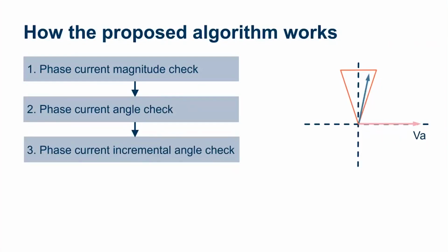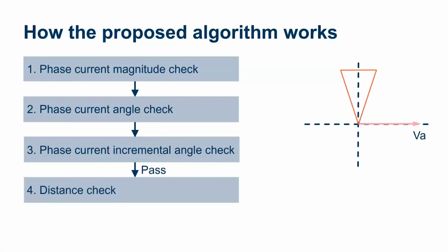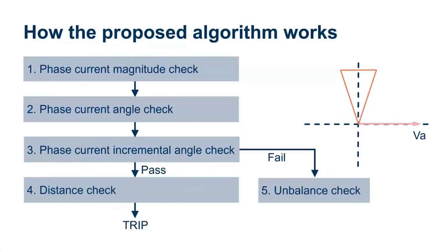And there's an animation of how we expect the current to look. Let me go back. See, it's moving into this window here. So if all three of those pass, we're going to run a distance check to see if it's on our line. We're going to calculate the distance to the fault. If all 4 of those pass, we're going to trip. Now, if we get to check 3 and we do not pass the incremental angle check, we're going to fail, and we're going to issue an alarm to the operator to say, you may have a current imbalance issue. So we're just going to alarm in that case.